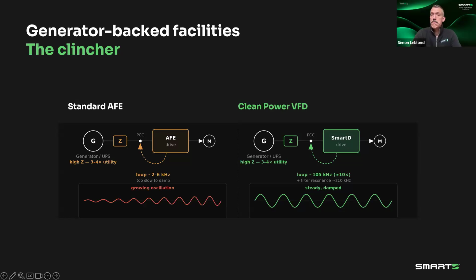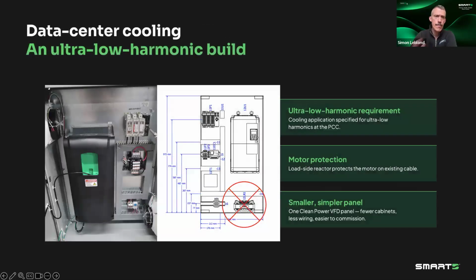So for data center design, this really becomes the center of your design phase and your consideration because they're not an edge case. We have been deployed in real data centers, meeting not only the low harmonic requirements specified at the point of common coupling, but also eliminating the load reactor to protect the motor and cables.